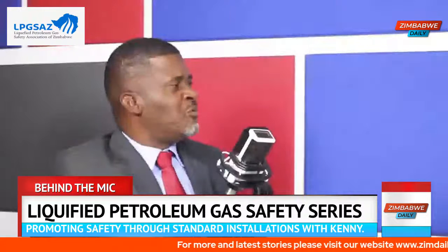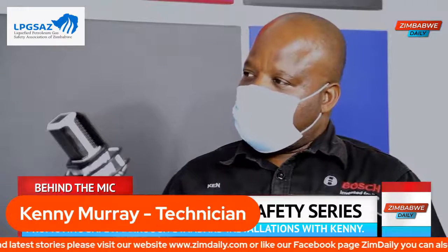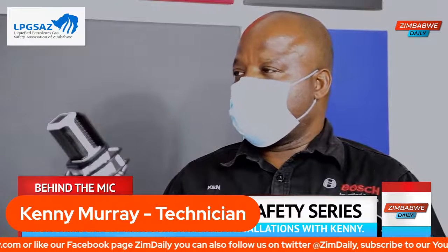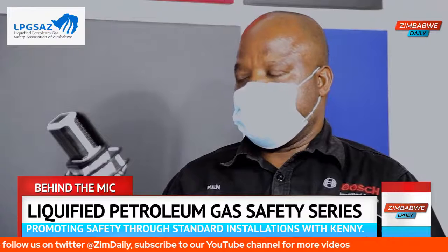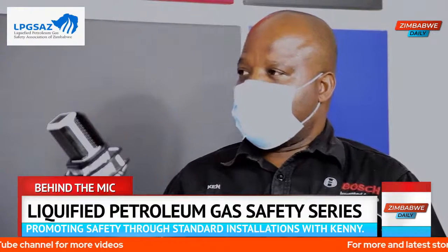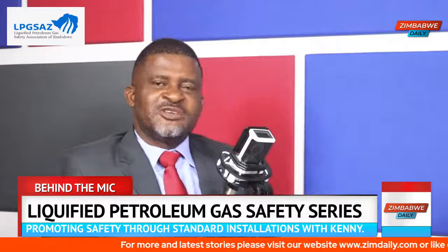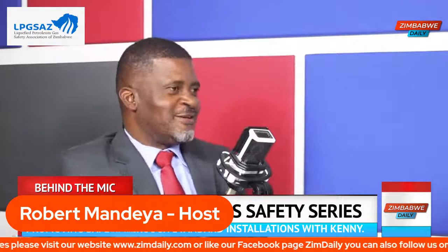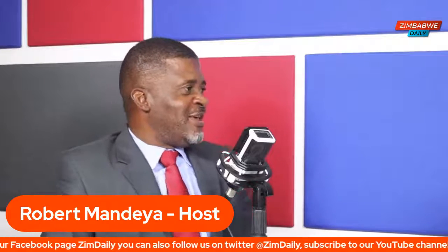So what is the danger in using the water pipes for gas installations? The ordinary water pipe, which you find in some smaller hardwares, is not suitable because the wall thickness is much thinner than what we call half hard pipe, class 1, class 2 going upwards. That water pipe is very thin and can wear off over time and then cause leaks, which you don't want in an installation. Oh, yes. That's quite interesting. Viewers, I'm talking to Ken Murray. My name is Robert Mandeya. We are here on the platform behind the mic, and I'm standing in for Yvonne. I hope you're following the discussion and the conversation that is happening here behind the mic.